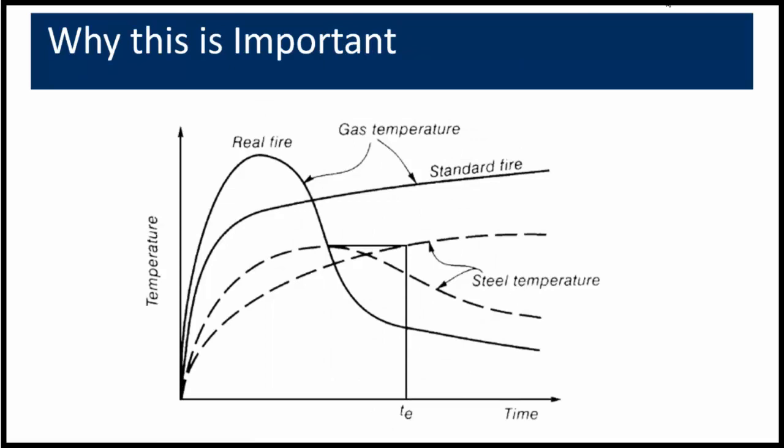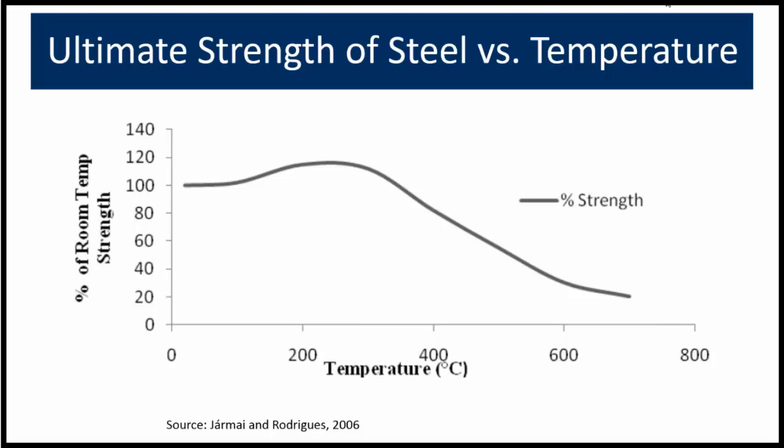This illustration shows the relationship between the interior temperature of a building and the effect on exposed steel. The curve labeled 'real fire' shows typical fire growth versus time with increasing temperature. As the temperature increases from an uncontrolled fire growing in the building, it will eventually increase the temperature of the structure. As the temperature of the steel increases, it loses strength and will not carry the loads. This is why structural components need to be insulated from the heat of an uncontrolled fire within a building.